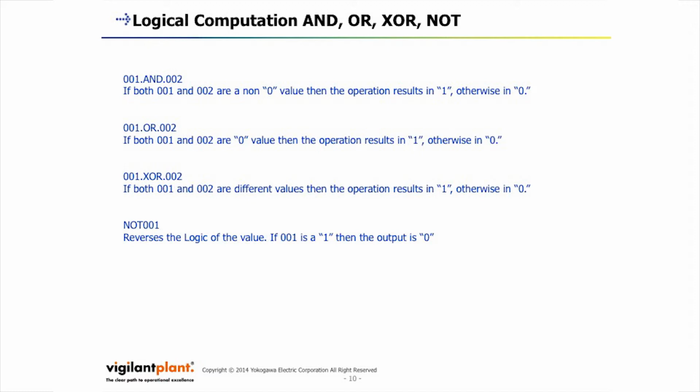001 and channel number 2. If both of those are true, you'll get a 1. If not, you'll get a result of a 0. Just remember that's an and statement, but that's the same kind of thing as multiplying those two channels together. But the difference was if you multiply channel 1 and 2, you'll actually multiply their values together. So if they were both 50 degrees C, you would in essence be multiplying 50 times 50, whereas if you take channel number 1 and it to channel number 2, you're just testing to see if they're both non-zeros, and your answer would be a 1, not basically 2500.